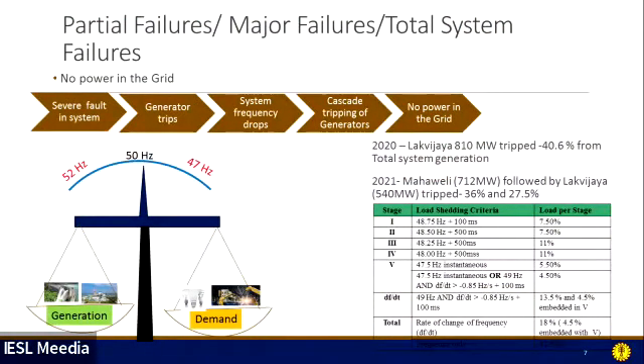So I'll take a little more time to explain how a total system failure happens. We can categorize failures as partial failures, major failures, and total system failures. What happened on 29th November was a major failure, which affects around 5 to 6 substations. Partial failures mean it affects 1 to 2 substations, and some 33 kV feeders may trip. The total failure is an entire system collapse.